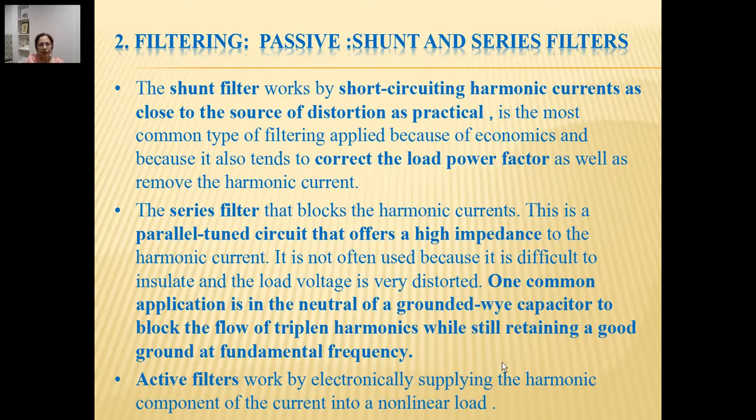These are the passive filters which we have discussed. Active as well as passive filters are used, and active filters work by electronically supplying the harmonic component of the current into a nonlinear load. So active filters are actually generating the opposing component of the frequency or harmonic order which we are trying to filter out, and it becomes a cancellation by having opposite polarity, same frequency, a harmonic component generated by the active filter, and so it can be instantaneously cancelling the harmonic effect.